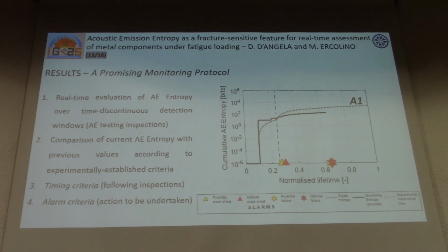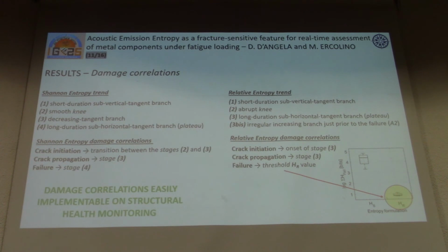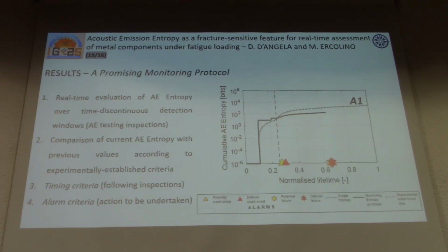The protocol is based on the ongoing, real-time comparison of the current acoustic emission entropy with previous values of entropy according to two experimentally established criteria that are based on the correlations we can see here. So the assessment of this comparison allows us to define in real time the timing criteria and the alarm criteria.